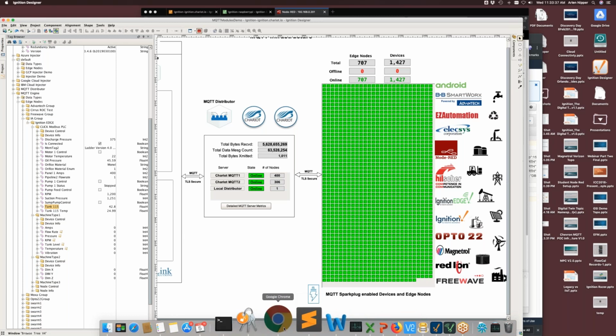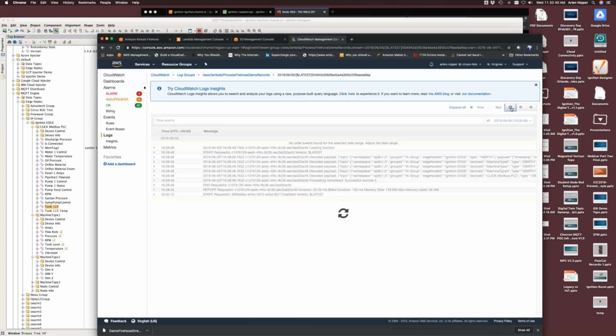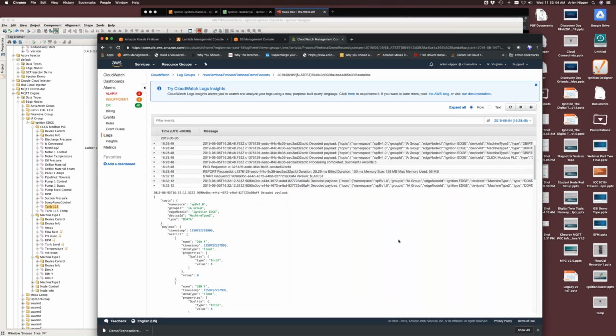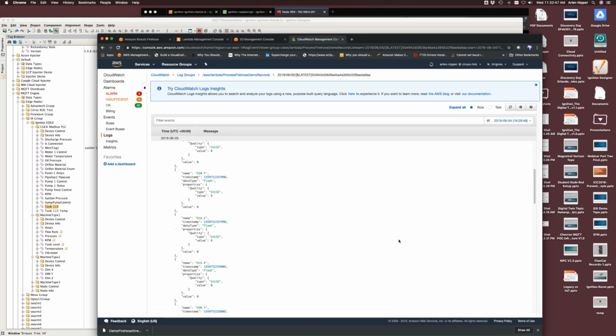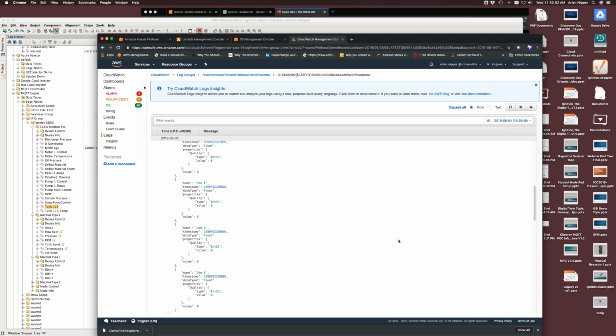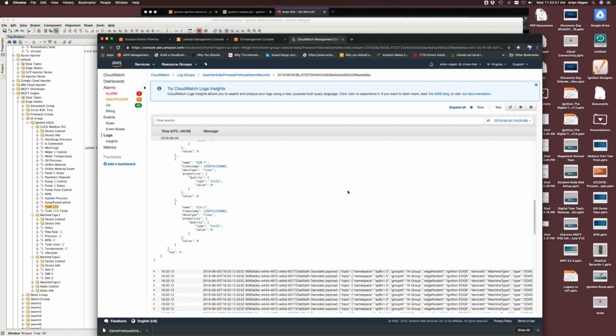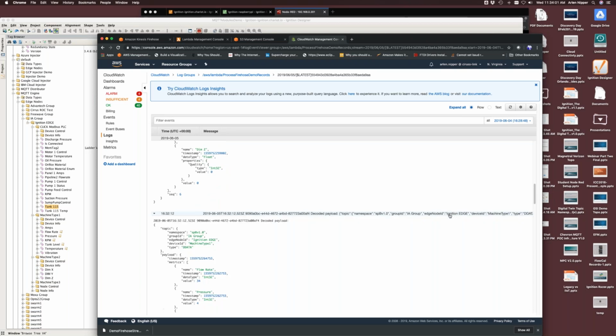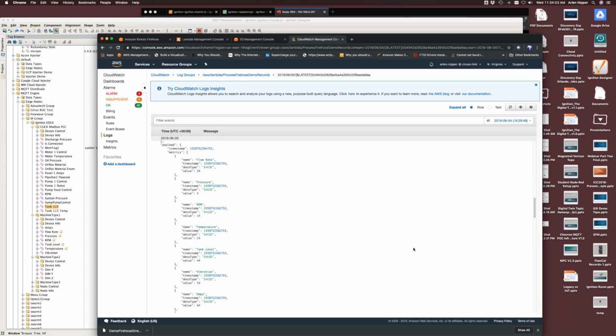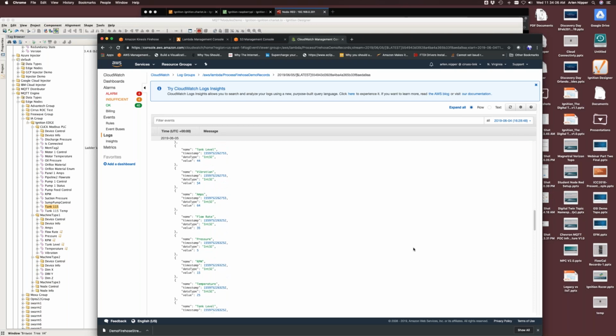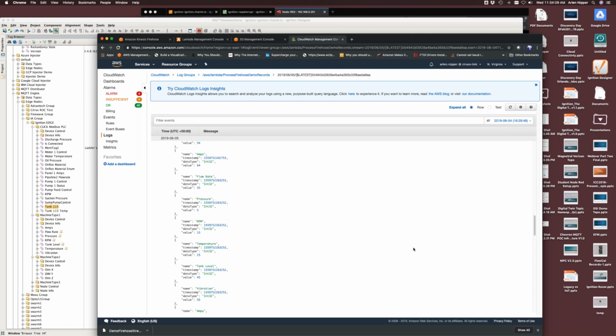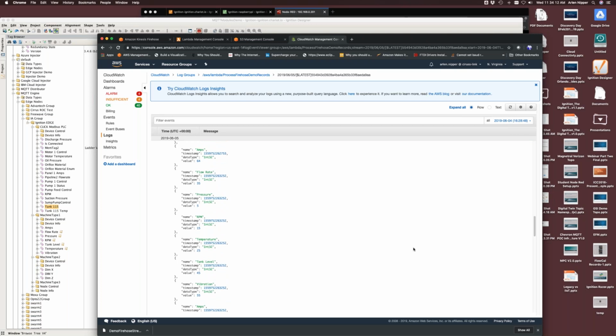So here, refresh this. And now we have a lot of messages, and you'll see that we're only publishing the data that changed. We're not publishing all of the Modbus values, but you'll see here that we have multiple dimensions, and they've got different timestamp values. If we go to the next message, you can see that we have multiple flow rates and multiple pressures, but those were sampled over that 2-second tag pacing period that we had. So we're efficiently using the Kinesis messages, but we're still getting all of the information up to the cloud.